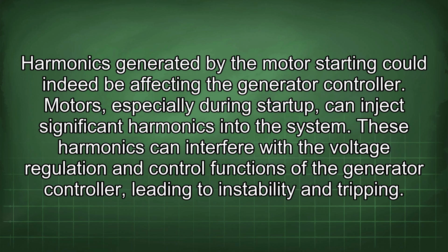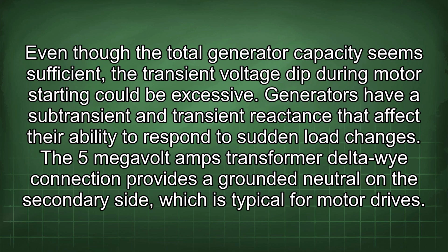Harmonics generated by the motor starting could indeed be affecting the generator controller. Motors, especially during startup, can inject significant harmonics into the system. These harmonics can interfere with the voltage regulation and control functions of the generator controller, leading to instability and tripping. Even though the total generator capacity seems sufficient, the transient voltage dip during motor starting could be excessive.